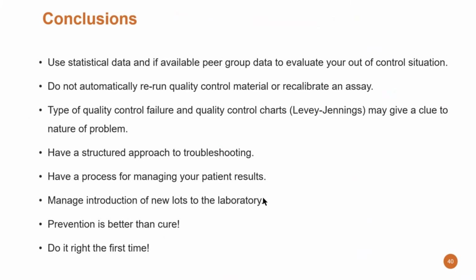The type of quality control failure and the quality control charts, using the Levey-Jennings charts, may give a clue to the nature of the problem. So values are too high, too low. That gives you an idea in which direction you may have to do the investigation. Have a structured approach to troubleshooting. Have a process for managing your patient results. This is usually also given by the management, that if you're outside of your QC limits, you're not reporting patient results. Manage the introduction of new lots to the laboratory, especially those of the reagents. They are causing problems more often in your daily QC. As usual, prevention is better than cure, and the ideal situation is to do it right the first time.